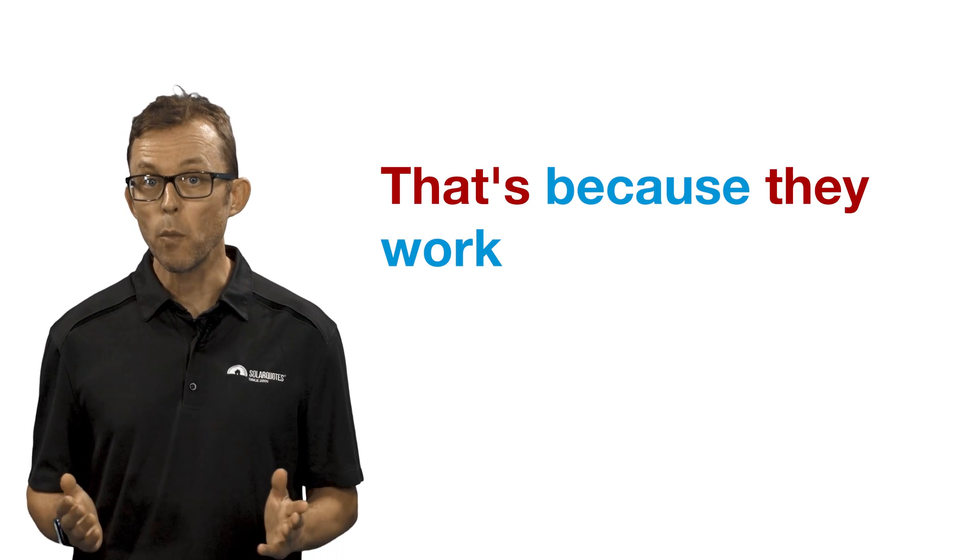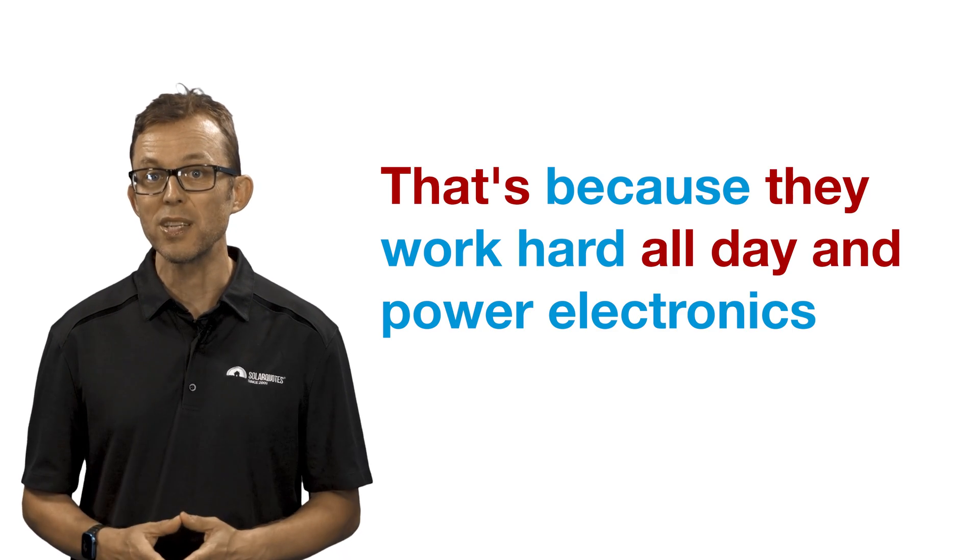What you might not realize is that the component of your solar system that is most likely to fail in the first 10 to 15 years is the inverter. That's because they work hard all day and power electronics can only do that for so long. I'd expect a premium inverter brand like Fronius to last a few more years than a budget inverter brand like Goodwe because of the way they are engineered and built. So for that reason, if you have limited funds, I'd recommend buying a premium inverter with budget panels instead of premium panels with a budget inverter.